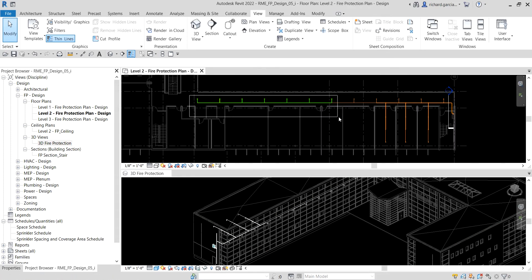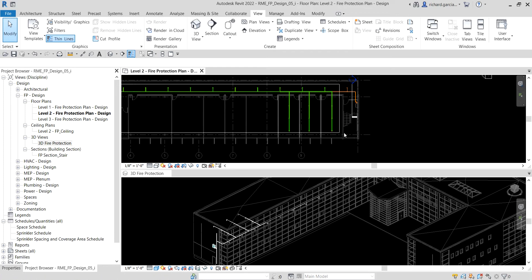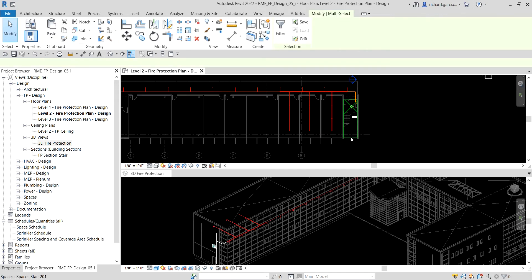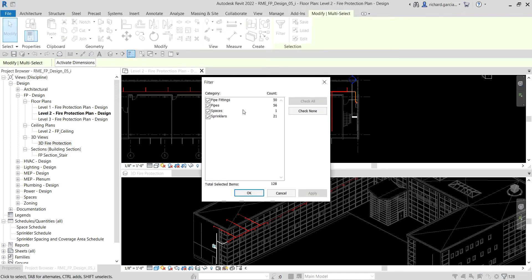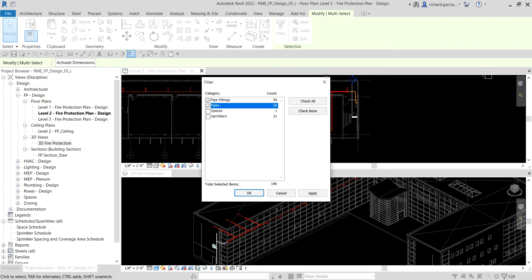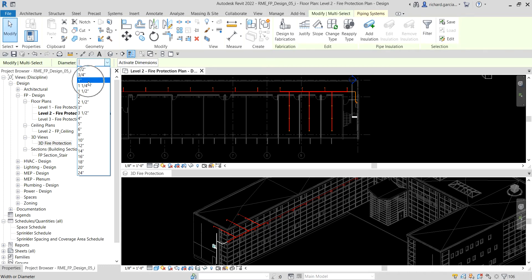In the floor plan view, I'm going to select from the upper left to the lower right of the building, then open the filter. I'll check none, then select pipe fittings and pipes. I'll click OK and then change the diameter to one inch, because that's the design requirement.